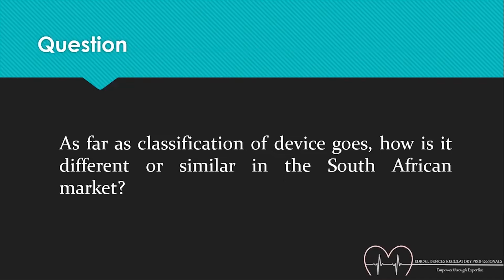The risk classification is from Class A to Class D, with A being a device that does not pose any danger or harm to the public, and D imposing the highest risk. Now, the manufacturer should decide if the product is a medical device or IVD based on the definition, and determine the intended use of the medical device or IVD. Also, consider all rules in order to establish the proper classification of the device.